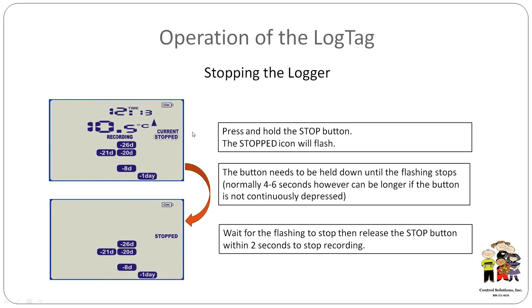With the logger ready to return to the docking station, I'll hold the bottom button again, just like in the starting sequence, pressing it down for 4 to 6 seconds. The word 'stop' will blink just like before, and once it's solid, the logger has stopped. Now we can bring it back to the PC without any false data in our collection.